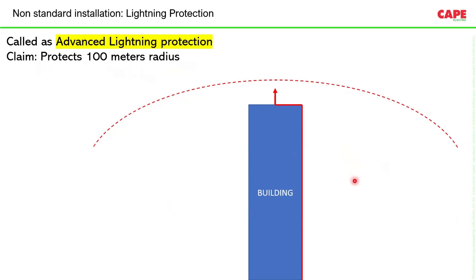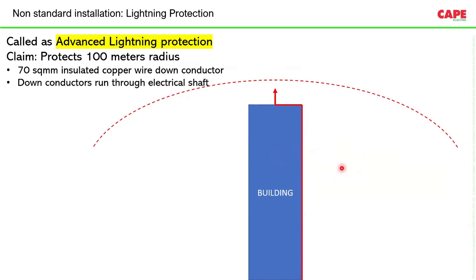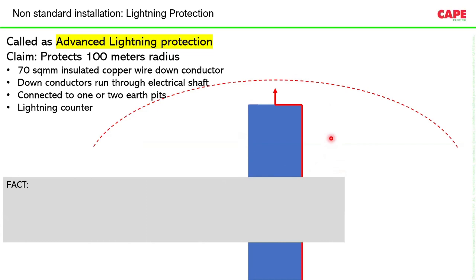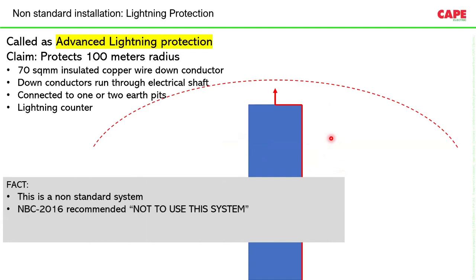So basically, these non-standard systems claim that they protect up to a 100-meter radius, and you need to have one down conductor, 70 square millimeters of copper wire, and one earth pit. So basically, one rod, one down conductor, and one earth pit. And this down conductor can be routed anywhere, most often through the electrical shaft. And then the owner of the building believes that he is protecting not only his building, but also all his neighbors. The only word to call this is a non-standard system.